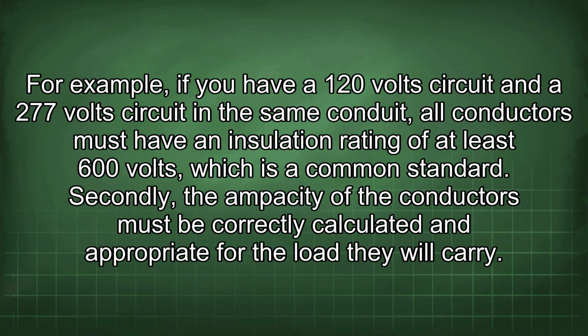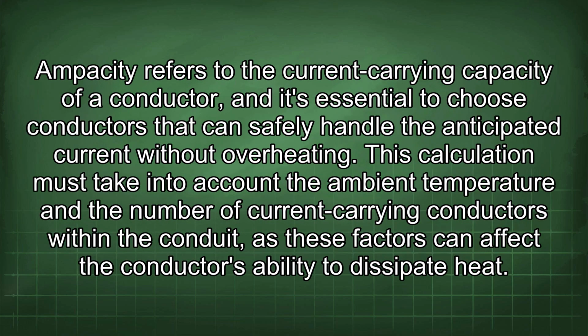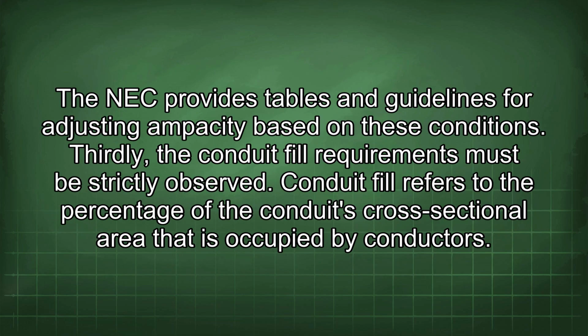Secondly, the ampacity of the conductors must be correctly calculated and appropriate for the load they will carry. Ampacity refers to the current carrying capacity of a conductor, and it is essential to choose conductors that can safely handle the anticipated current without overheating. This calculation must take into account the ambient temperature and the number of current-carrying conductors within the conduit, as these factors can affect the conductor's ability to dissipate heat. The NEC provides tables and guidelines for adjusting ampacity based on these conditions.